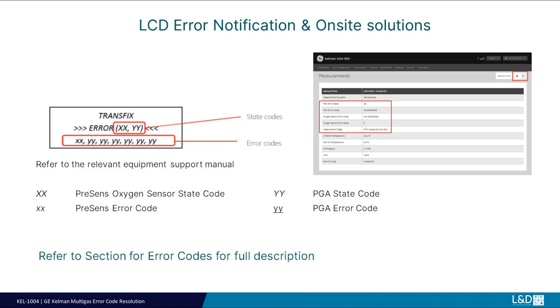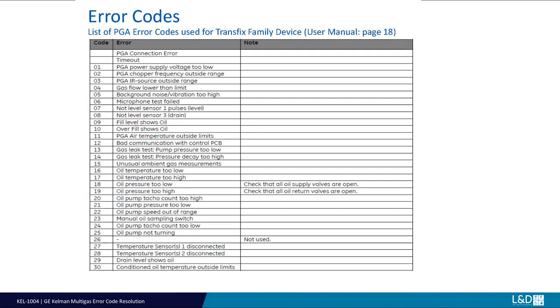Errors are reported using a sequence of double digit codes for the PGA and the oxygen sensor if enabled. The PGA error state denotes the most recent state within the measurement cycle where the error occurred. All errors are listed as error codes and the associated hexadecimal in brackets allows the most recent state to be identified.